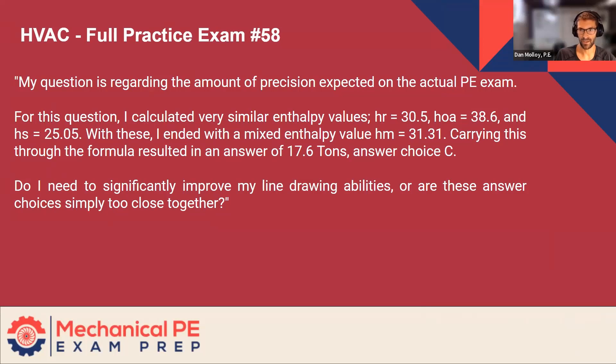For this question, I calculated very similar enthalpy values. Enthalpy return is 30.5, the outside air enthalpy is 38.6, and the supply enthalpy is 25. With these, I ended with a mixed enthalpy value of 31.3. Carrying this through the formula resulted in an answer of 17.6 tons, answer choice C.